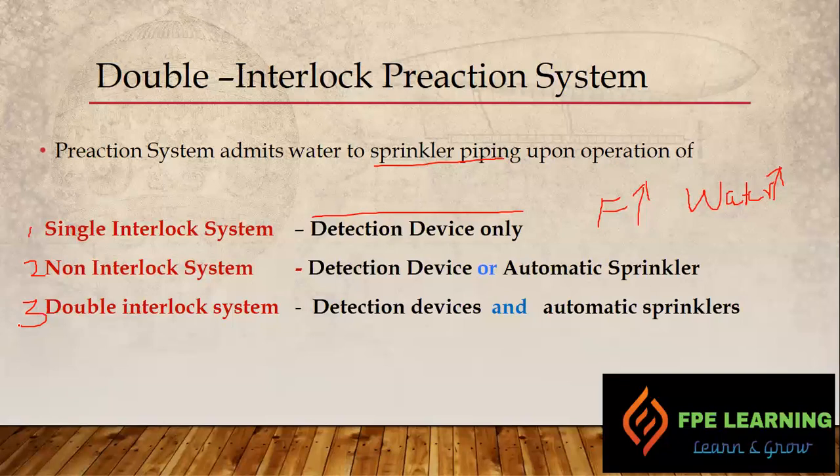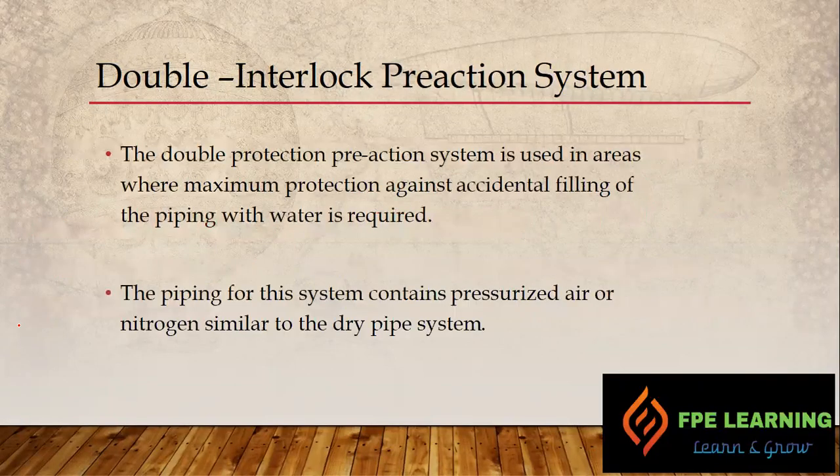So let's look at the double interlock system in detail. This system is mostly applicable in areas where maximum protection against accidental filling of the piping with water is required. The piping in this system contains pressurized air or nitrogen, similar to the dry pipe system. Remember, in the dry pipe system, once a sprinkler activates, the nitrogen or air pressure reduces, causing a differential pressure, and then water enters the piping. This system works in the same way after the deluge valve — as a dry pipe system.